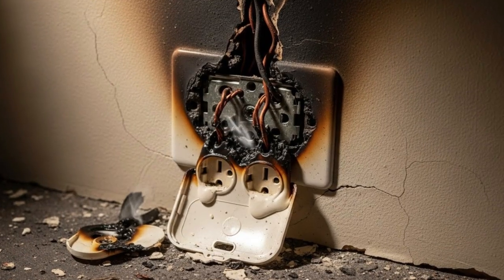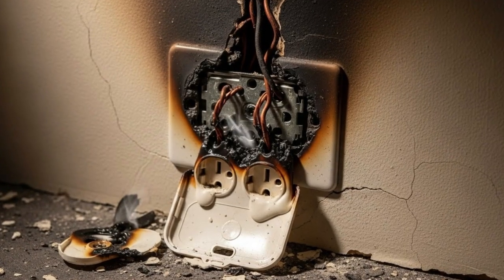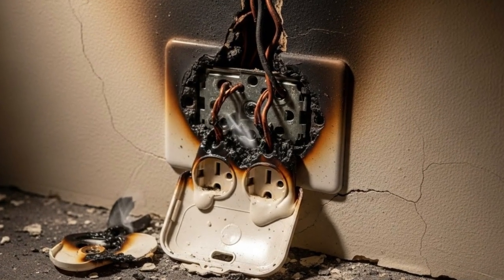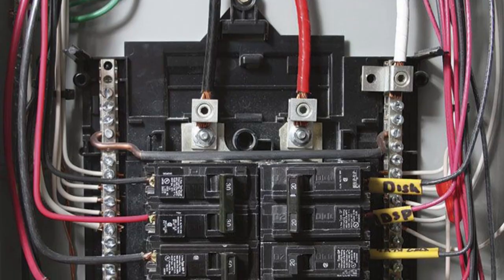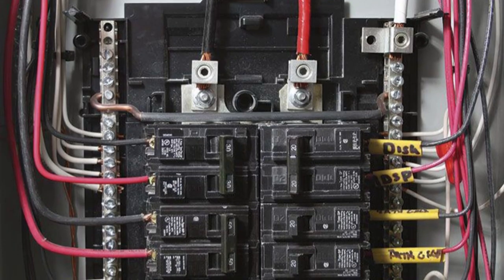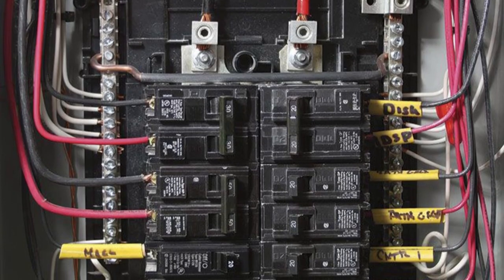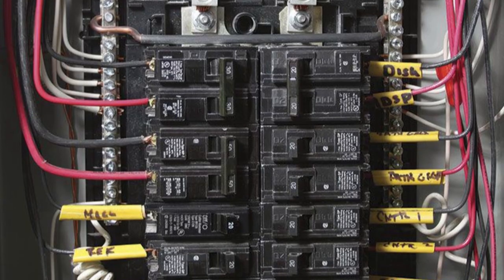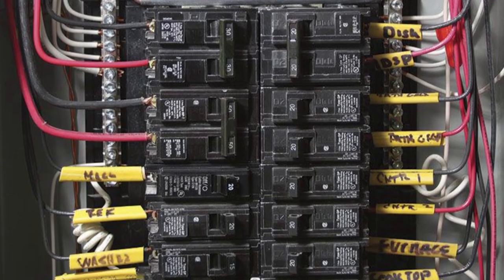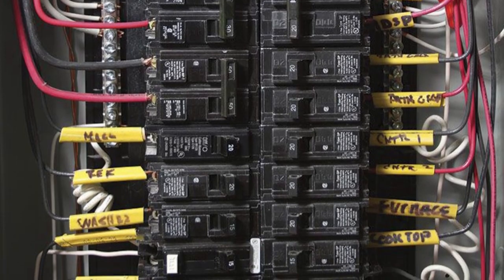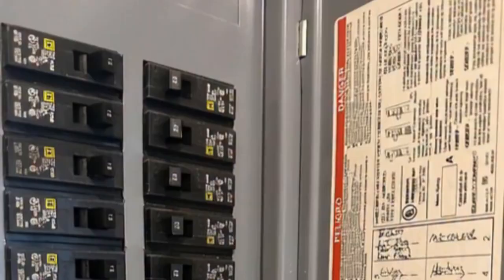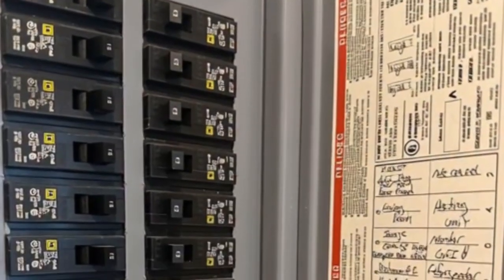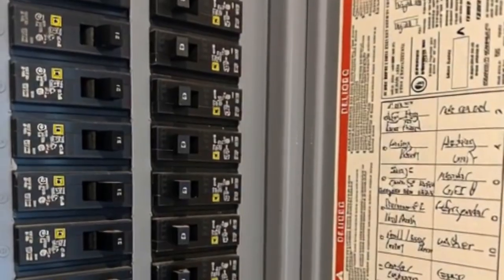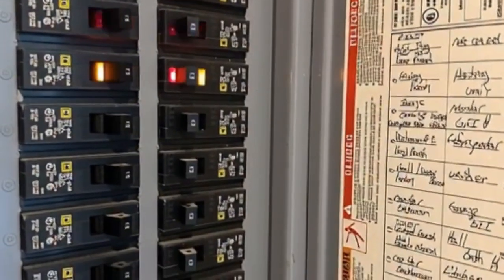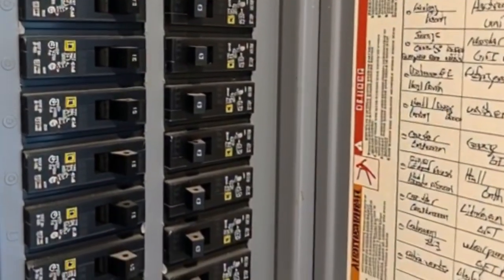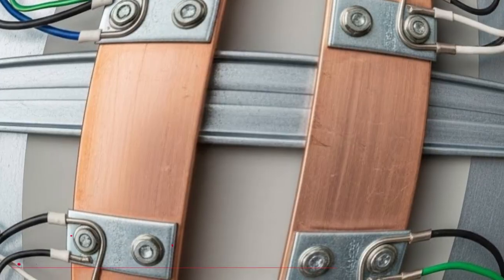Here's where the confusion starts. Most people think the main breaker only trips from overload. Too many things running at once, but that's only one reason a breaker trips. Main breakers also trip from short circuits, ground faults, internal failures, and external problems that have nothing to do with how much electricity you're using. When your main breaker trips without load, the breaker is detecting a problem. It's doing its job. The question is, what problem is it detecting? Let's go through the 5 most common causes.